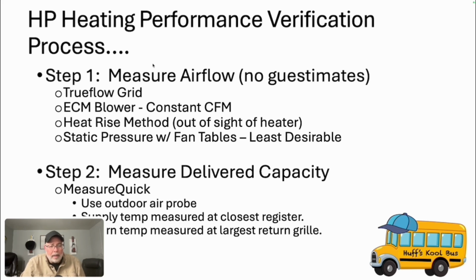Now, I will tell you this: if that indoor unit is in any area that's unconditioned, such as an attic or an unconditioned crawl space, one of the things that I like to do is take a measurement, not only at the return grill, having an air probe at the return grill like we would normally do, but I also like to take another return temperature measurement at the air handler and compare and see if there's any difference between the temperature at the return grill and the temperature at the air handler itself. Why would I do that? Well, what if there is some air leakage and I'm sucking in attic air or sucking in crawl space air? Think about what that is going to do to my system. Now, if I uncover that and I find that problem, guess what I'm going to do? I'm still going to measure that capacity the way the system stands, and then seal that up and then retest again. And that way, again, I can show the percentage of improvement I made on this system.